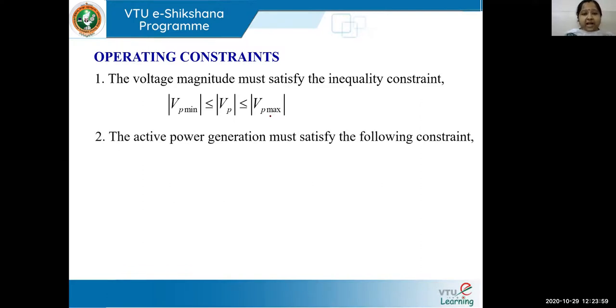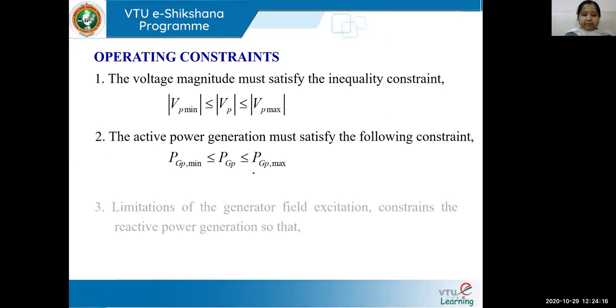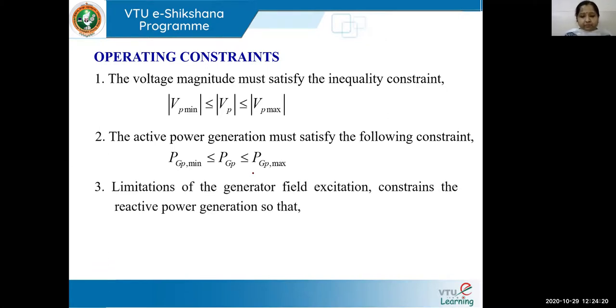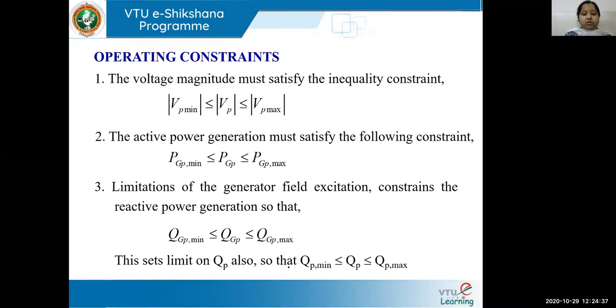The second operating constraint concerns active power generation: PGP_min ≤ PGP ≤ PGP_max. The generation at that particular bus must maintain this limit. The third constraint is reactive power: limitations of generator field excitations constrain reactive power generation, expressed as QGP_min ≤ QGP ≤ QGP_max.